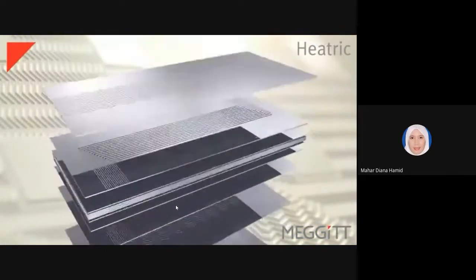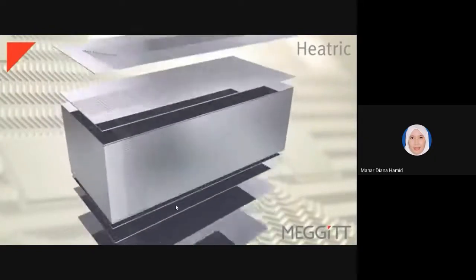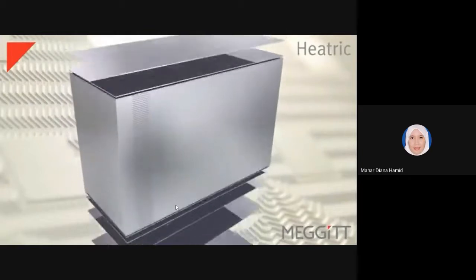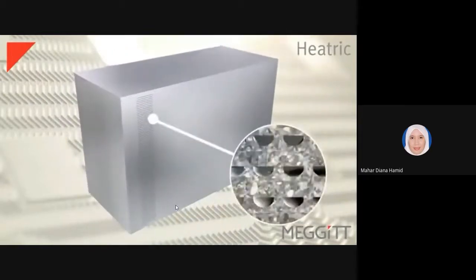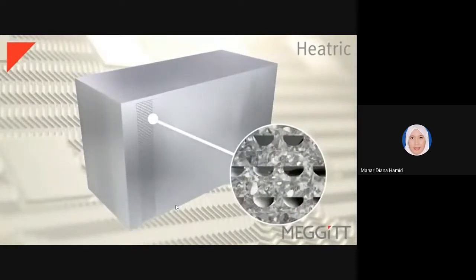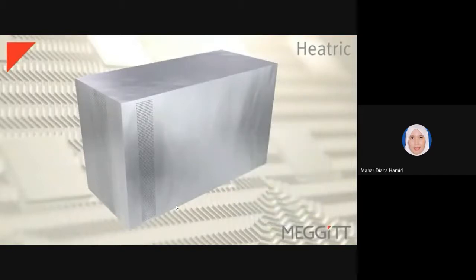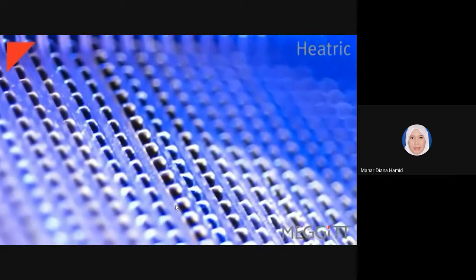The etched plates are then stacked alternately, cold, then hot, and diffusion bonded together. Diffusion bonding is a solid-state joining process where, under high temperature and pressure, grain growth takes place at the interface of two metal surfaces in contact with each other. The resulting bond achieves the same mechanical strength as the original material. The diffusion bonding process does not employ any braze, flux, or gaskets in the construction of the heat exchanger core. This bonded core behaves as a single metal block with engineered holes running through it. It can then be machined and welded using conventional fabrication techniques.